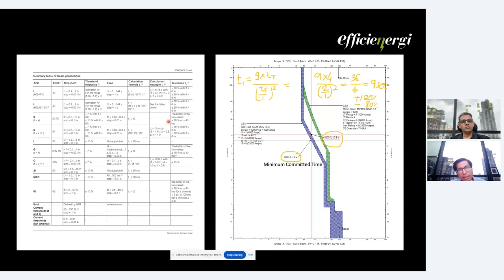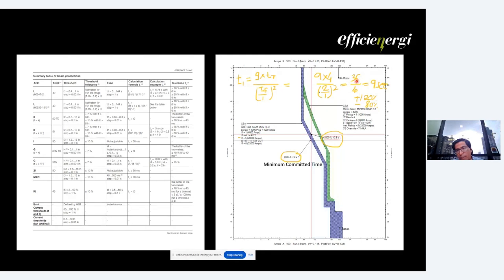For this particular TCC, they have given this equation, which is 9 times TR divided by fault current into the set current, squared. So you can see here we have the setting of IR is 1, TR is 4. So 9 into 4, and then let's say we are measuring for 2 times the current, that is 8000, 4000 into 2. So we have a fault current of 2 times the IR value. So 2 divided by 1, squared, that is 4 again. If you calculate, this comes to around 9 seconds. So the theoretical value for 8000 ampere fault current, the operating time should be 9 seconds.